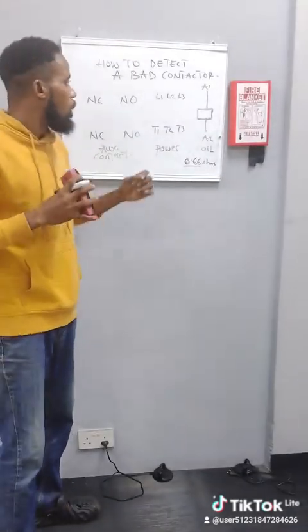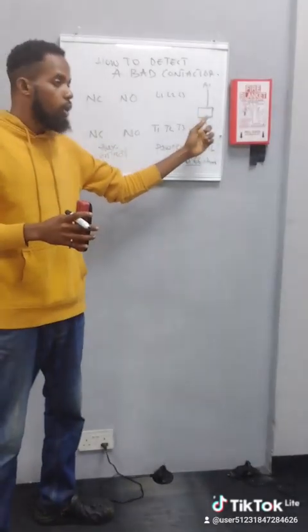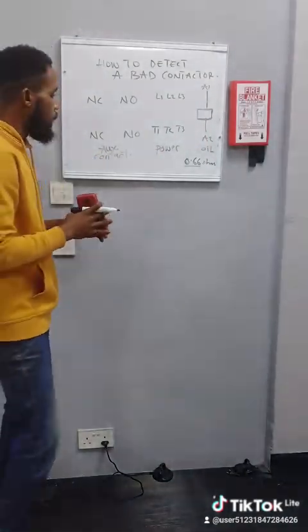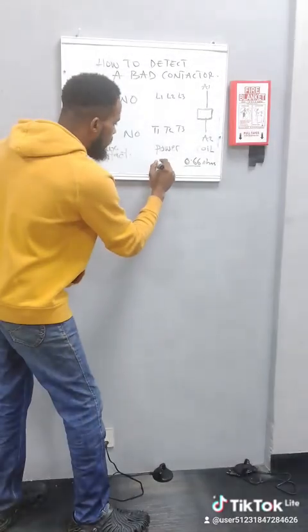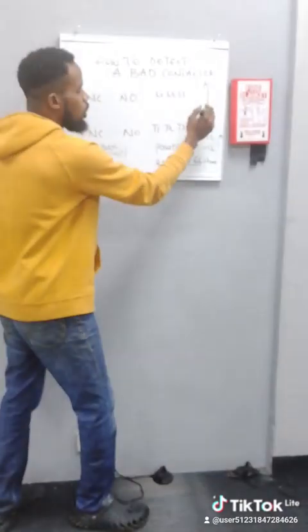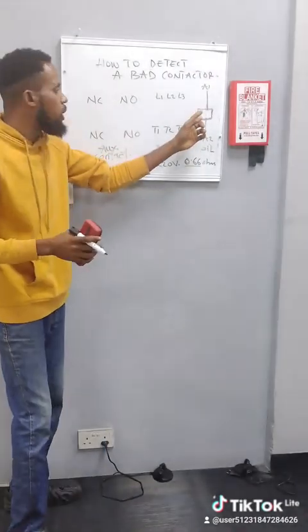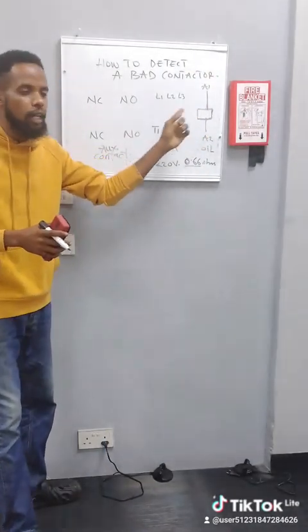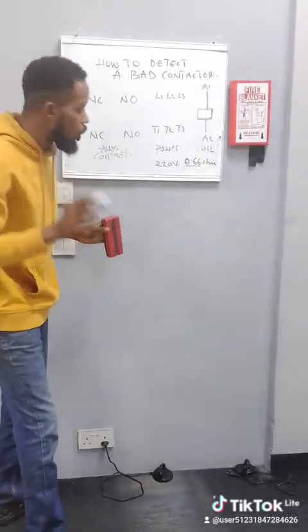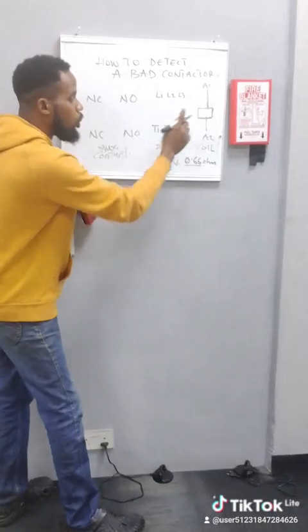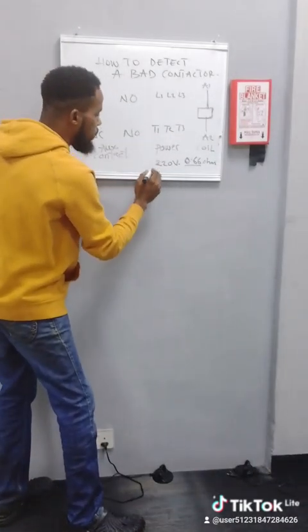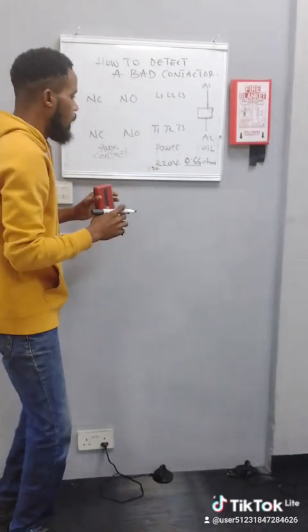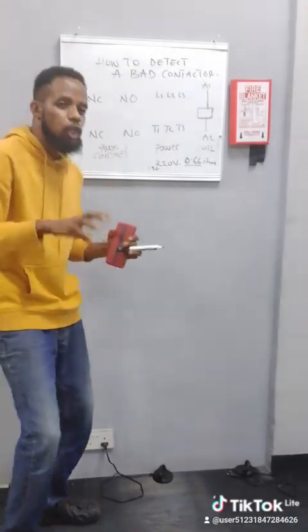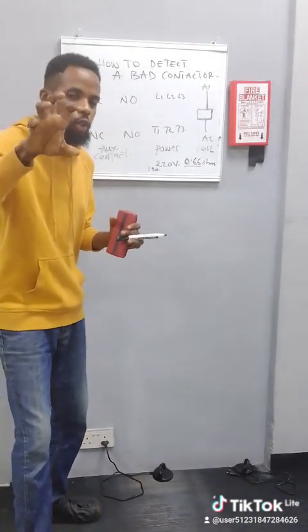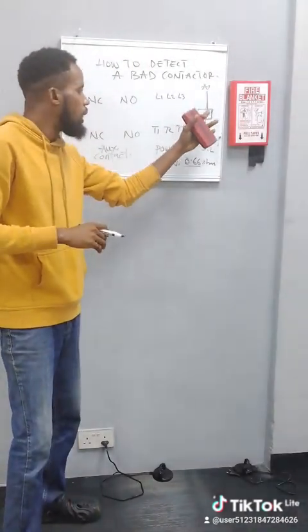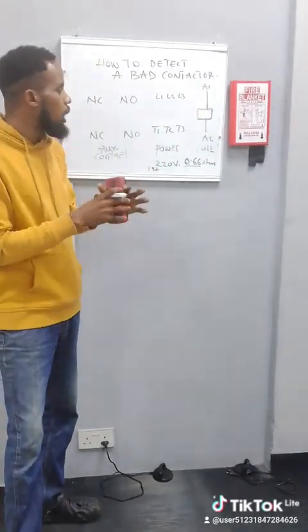As a technician, as an electrician, firstly you need to know the kind of voltage that is going to your coil. Normally 220 volts is the appropriate voltage that the contactor coil needs. But if the voltage that is going to energize the coil is not up to 200, maybe it's 150 volts, it will not energize. It will be closing, open, close, open. It will not close. The coil will not work, and the contactor will not work.